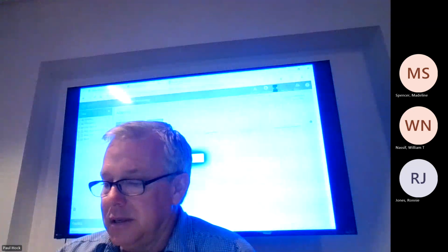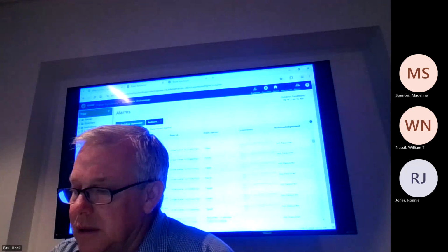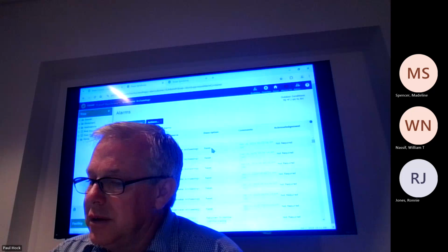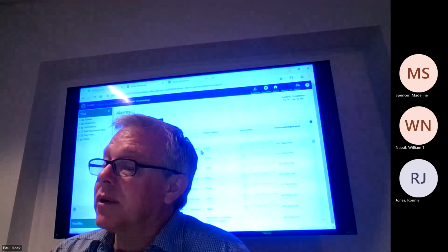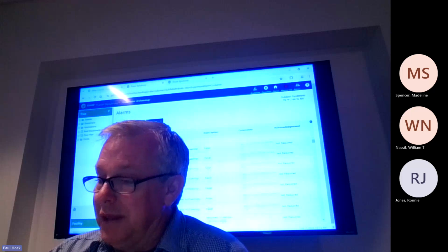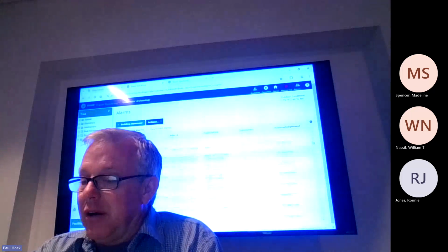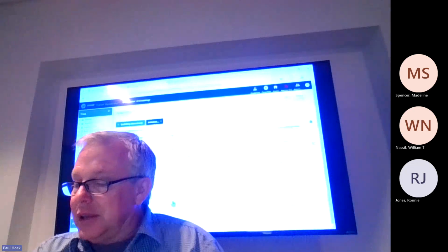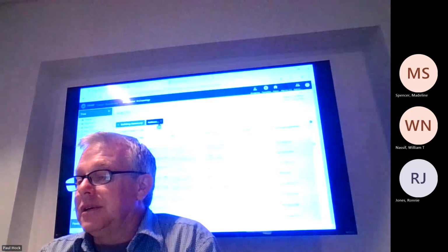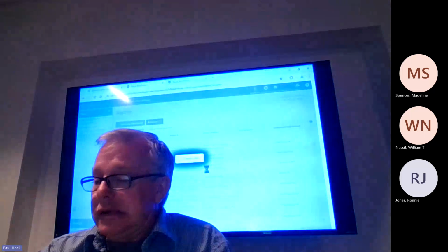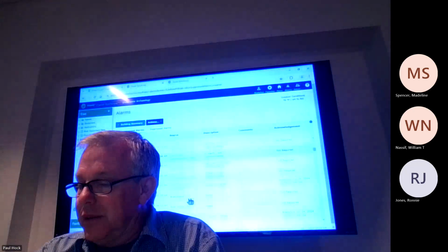There's an alarm. Let's see what that alarm is. We had some resets, power issues. So this means that the FC reset. That means it either lost power or somebody turned it off. I'm thinking that was a power bump. Multiple of them. That was when that big storm hit here. Oh, the 16th was. That was that Monday, right? Yeah. So I told you that the condenser tripped. Duct static pressure. You can just click on them. I didn't even think about the storm that was here. Everything was underwater, wasn't it? Boathouse duct static. Okay, that makes sense.